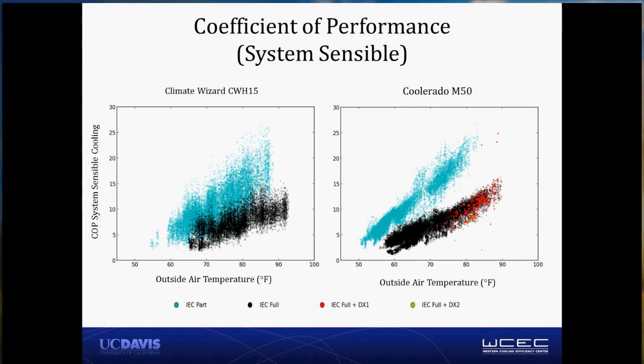So in those hours when you can get by with the cooling delivered at part speed, you can run with a coefficient of performance that's well above 20, and it is actually increasing, you note, as outside air temperature increases. When you need the additional cooling capacity at full load, I think we can expect, at peak, which goes beyond the data that was available during this time period, the trend shows you should mark a coefficient of performance around 15. Where would a standard unit line up? In the field, we've been marking coefficient of performance for standard machines around 2.